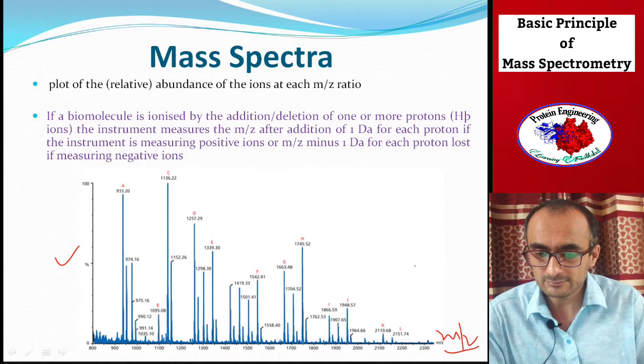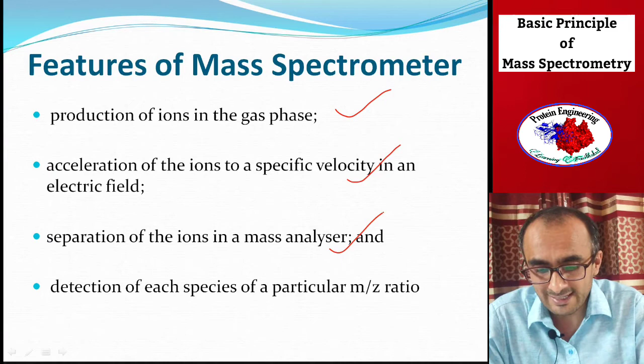There are 4 features of a typical mass spectrometer. First, production of ions in the gas phase, which happens in every mass spectrometer: the analyte is converted into ions in the gaseous state. Then those ions are accelerated to a specific velocity by applying a high voltage. The beam of those ions is analyzed in a mass analyzer, which gives the calculation of m/z of those ions. And finally the beams of specific m/z ions are detected, separately or simultaneously, by a detector.